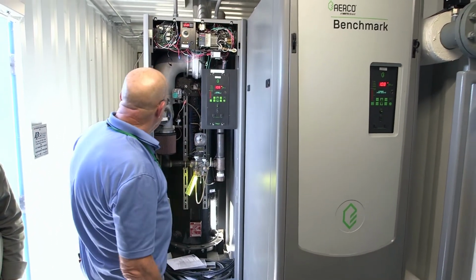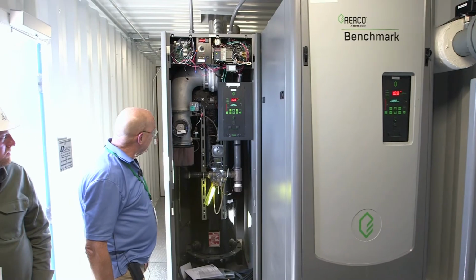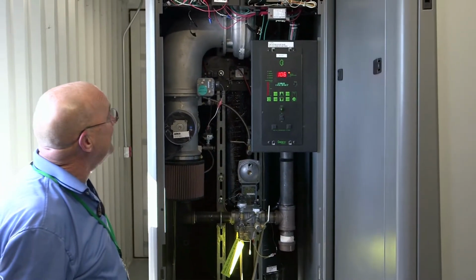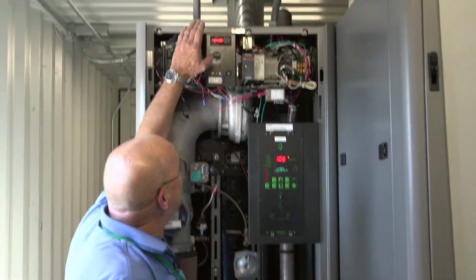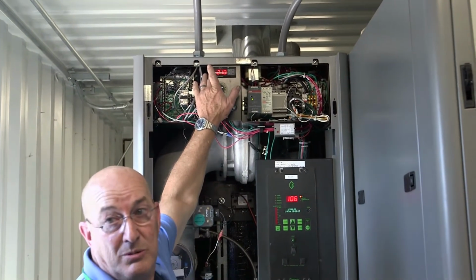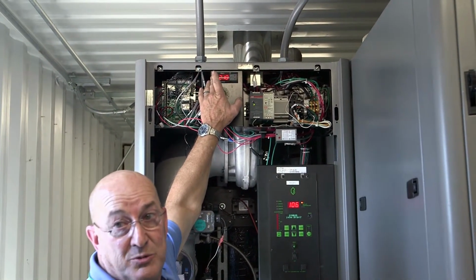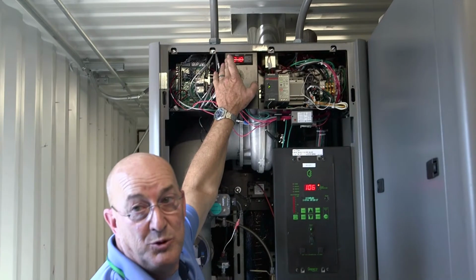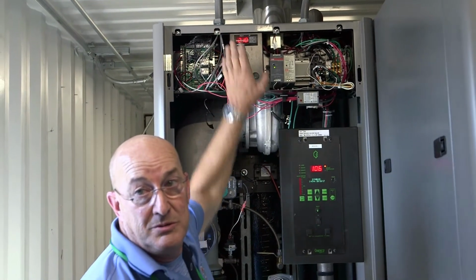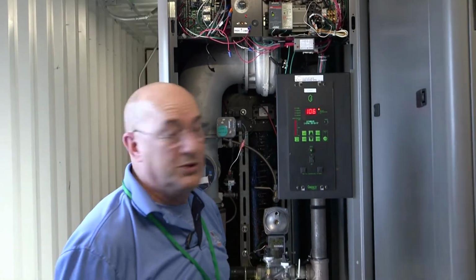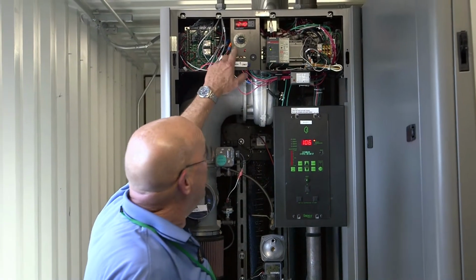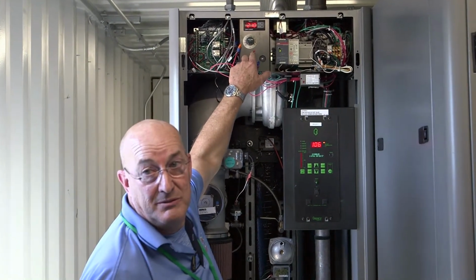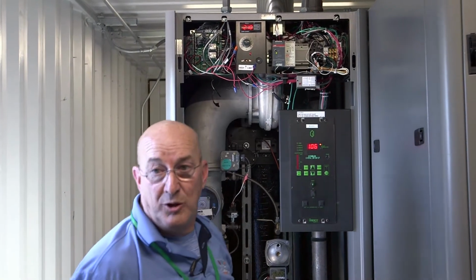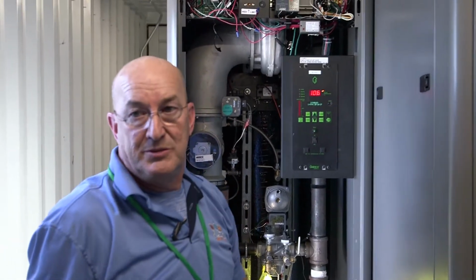This is actually what it looks like inside the cover. This here is your high limit control. It's set for 210 degrees. If the boiler temperature goes up to 210 degrees, it shuts them down. It will not come back on unless you push this reset button. There's no harm in pressing the reset button once.